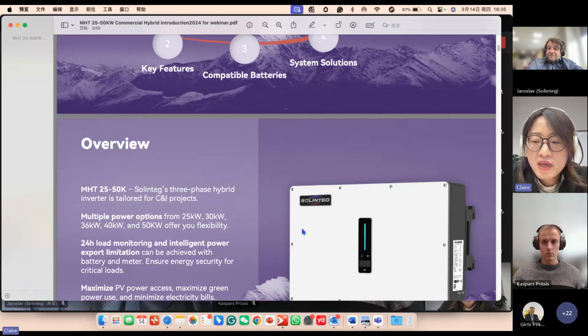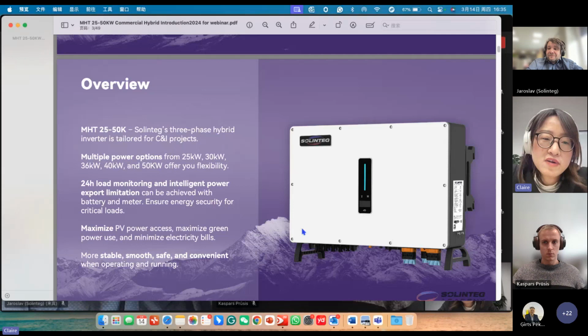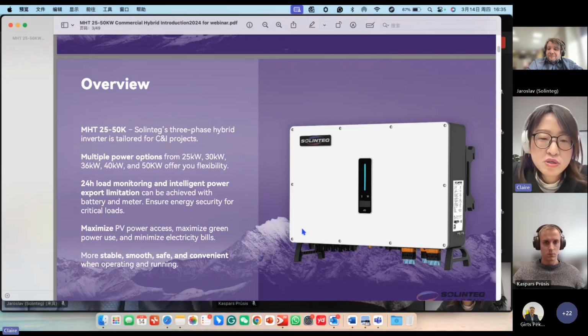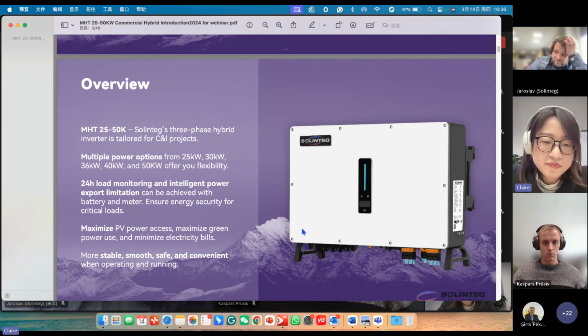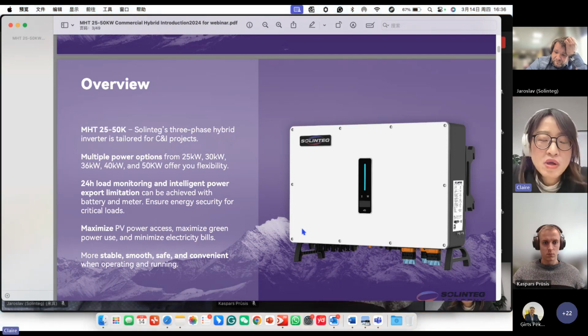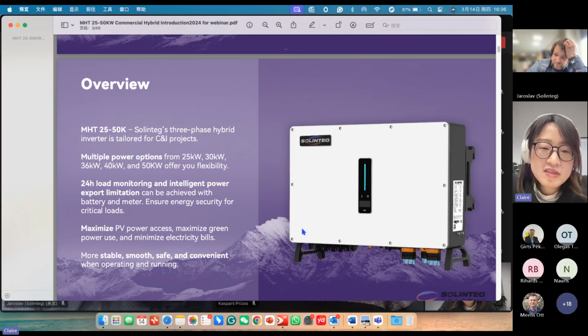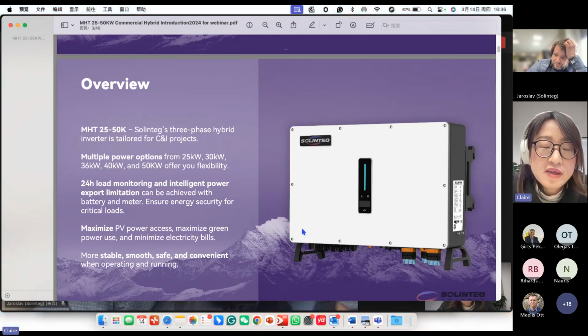In the beginning, we can see the Solinteg 25 kilowatt inverter is designed for commercial and industrial projects. So we have a very wide power range, including 25 kilowatt, 30 kilowatt, 36, 40, and 50 kilowatts, which offers customers greater flexibility. Paired with our smart meter, our inverter can realize 24 hours monitoring, load monitoring, and also intelligent power export limitation. With 110% AC overloading continuously, and 150% AC overloading for 60 seconds, we can ensure energy security for the critical loads when the power grid goes off.